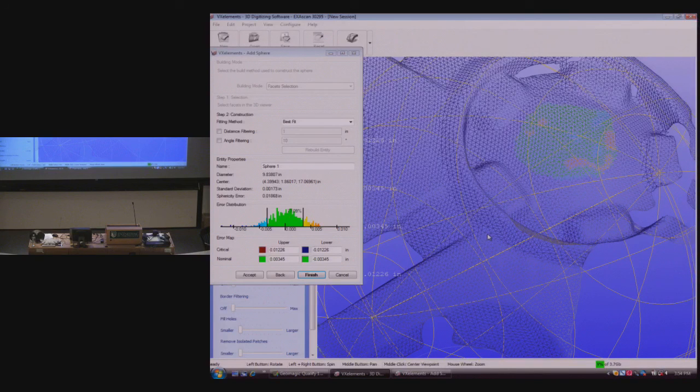There is a whole family of different types of scanners out there, where we merge photogrammetry, structured white light. There's a lot of different ones. But let's just talk about this one right now since we don't have a huge amount of time. So what I'm going to say is, and I wrote this down earlier, the error equation for this, I don't know if you guys think in inches or metric, this is 20 microns. That is your baseline error. So that means that thing is no more accurate than 20 microns.